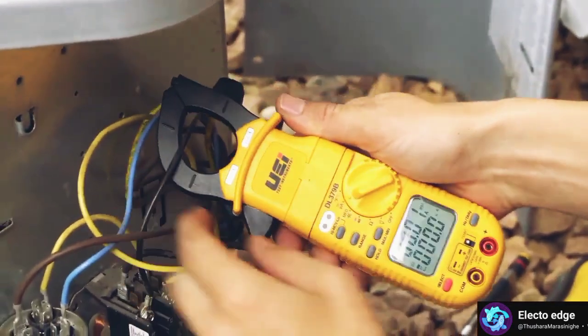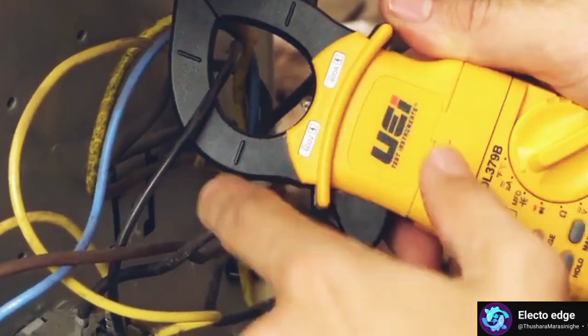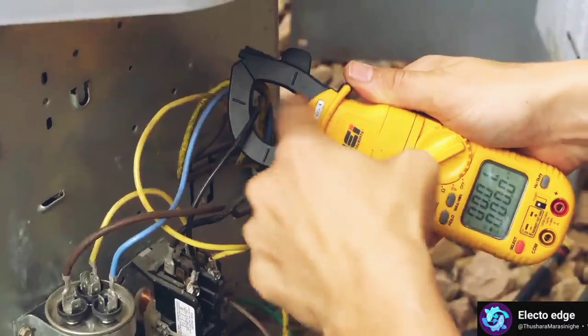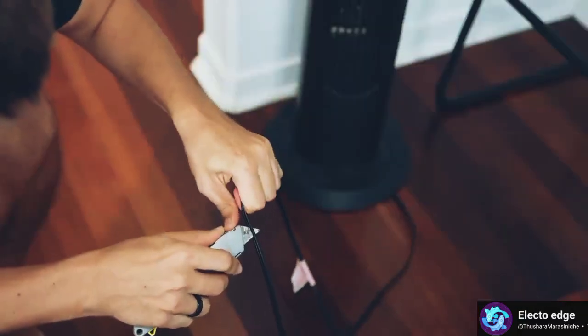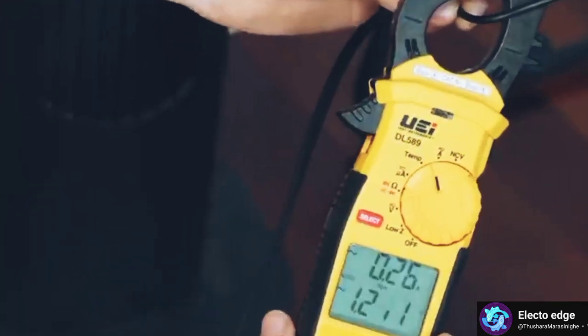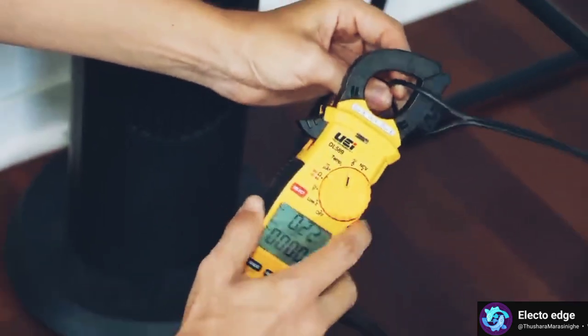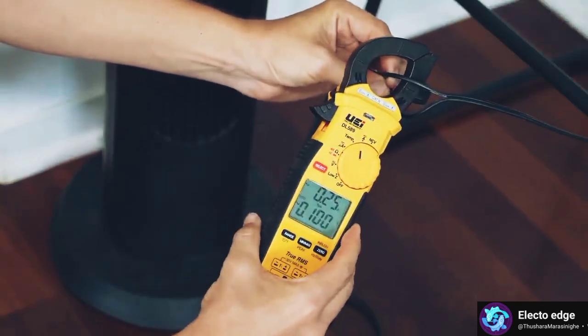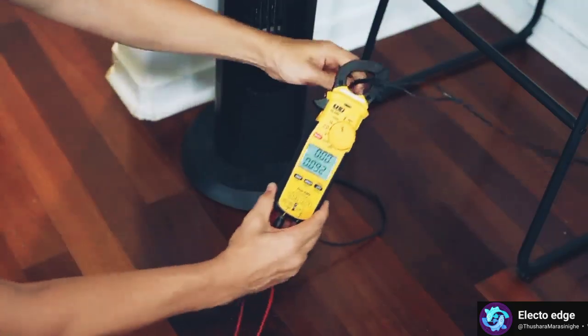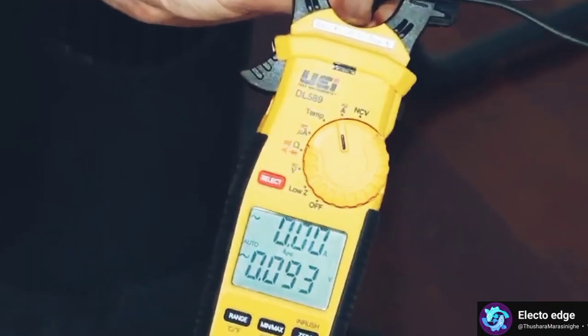And it doesn't matter if you put your clamp on the neutral or the hot wire, both of them should give you the same read. One important thing to note is that the hot wire does need to be isolated from the neutral. If you put your clamp around both wires, the hot and the neutral are going to cancel each other out and you're not going to get any reading.